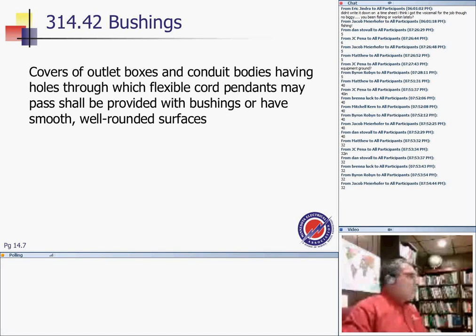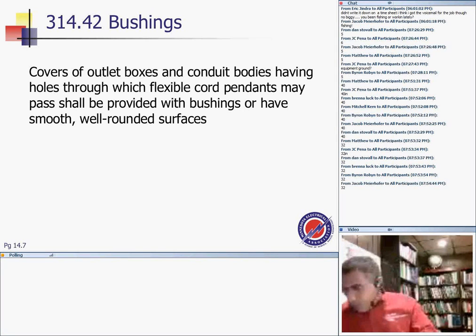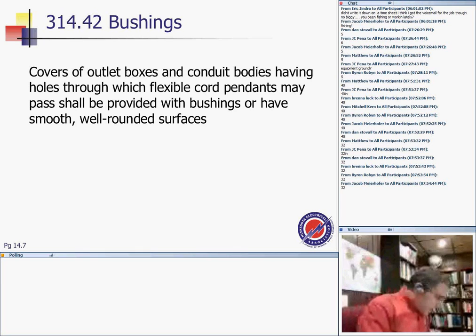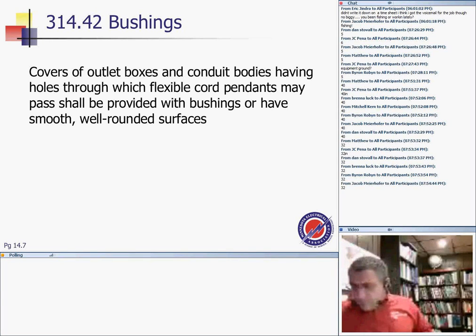Bushings. Outlet boxes having holes through which flexible pendant cords may pass shall be provided with a bushing or have smooth, well-rounded surfaces. So that's insulating bushings, guys. Okay, about bushings, and covers of outlet boxes with flexible cords. Both the bushings or adapters are required to protect the conductors. So that's basically the adapters and the bushings that we need.